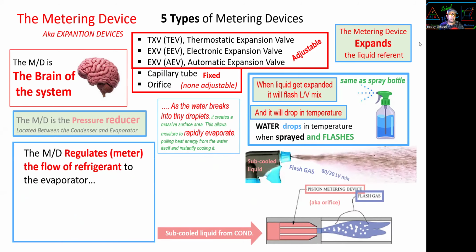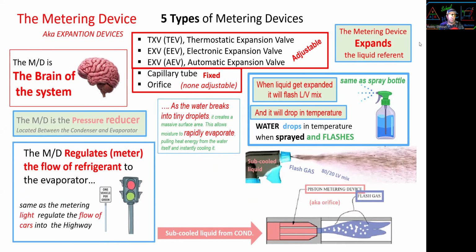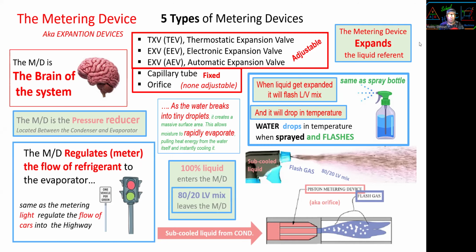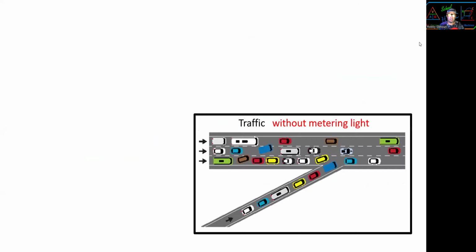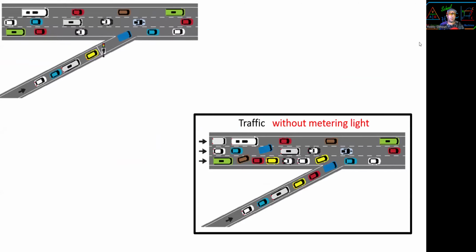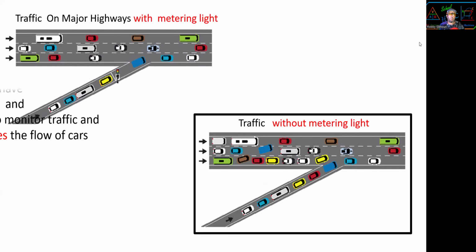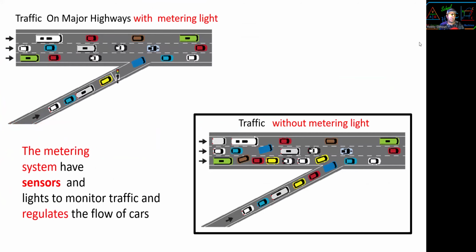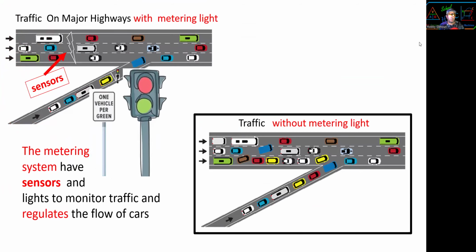The metering device regulates the flow of refrigerant to the evaporator, same as the metering lights regulate the flow of cars onto the highway. 100% liquid enters the metering device and an 80-20 liquid vapor mix leaves the metering device. Traffic without a metering light: traffic on major highways. The metering system has sensors and lights to monitor traffic and regulate the flow of cars.